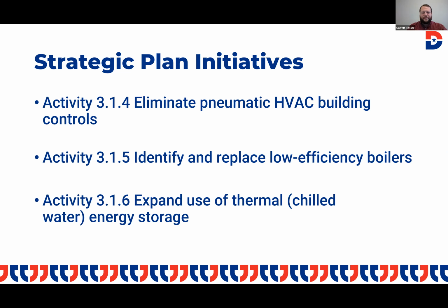Eliminating pneumatics, again, still present on 3 of our campuses; the other 4 are all DDC. Low efficiency boilers—we still have some standard 80% efficient boilers that need to be moved to condensing boilers. Expanding the use of thermal storage is another big opportunity for us that we're at least going to get going on at one other campus, because it allows us to shift our load, helps us out on the procurement side, and also certainly during that 4CP period.